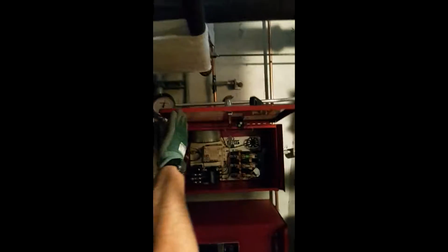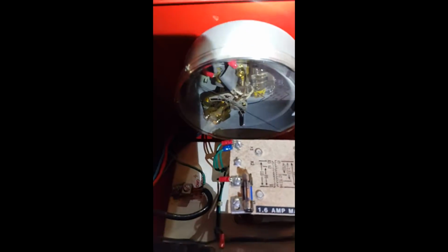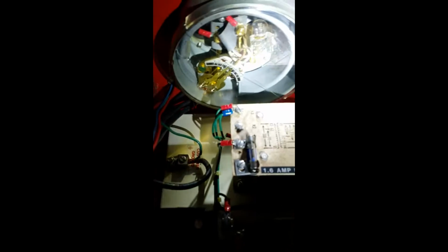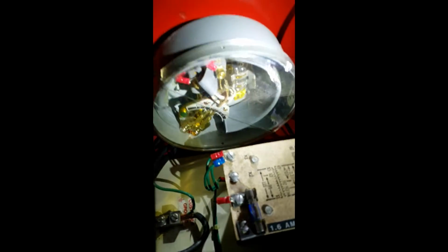And this is your mercury switch here. If you guys ever work on this pump, there's a little vial in here full of mercury. I really recommend that you don't break it, because mercury is kind of toxic. If you look at the settings right there, it's set to start at 150 and stop at 170. The bottom fork starts at 150, and the top one is at 170.